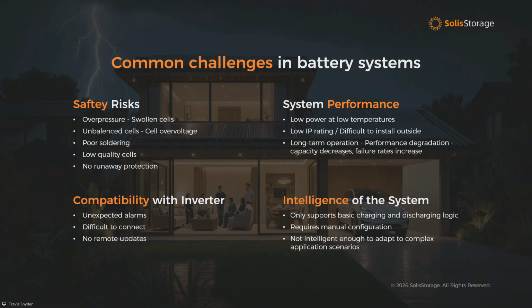Moving on to system performance: the IP rating of all the first batteries was like IP20. There was low power at low temperatures, caused by the quality of the cell and the internal resistance, plus compatibility issues with the inverter. In the beginning only a couple brands were making batteries, like Pylon being one of the first, then a few others came into the market, and there were a lot of issues with inverters at that time. The intelligence of the system meant components couldn't talk with each other, and there were a lot of different configurations.